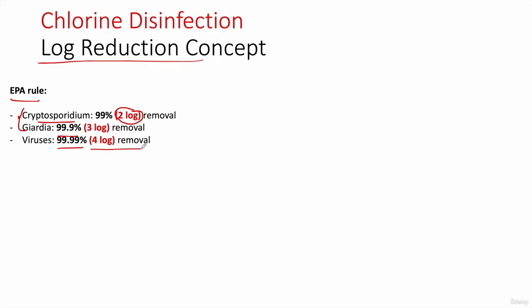Now, between parentheses, I will zoom in a bit on Cryptosporidium. If we have high concentrations of Cryptosporidium in our water, it is better to consider UV disinfection, since chlorination is not that effective on this kind of protozoa. We need very high concentrations of chlorine to remove Cryptosporidium.